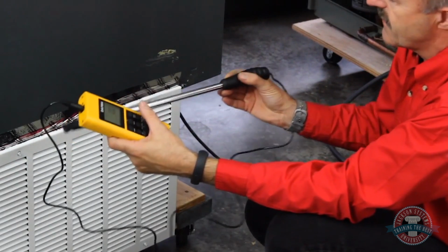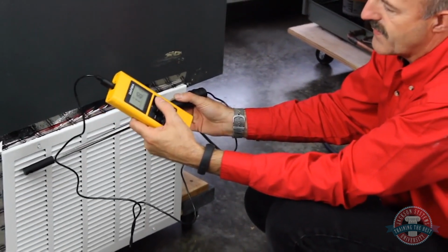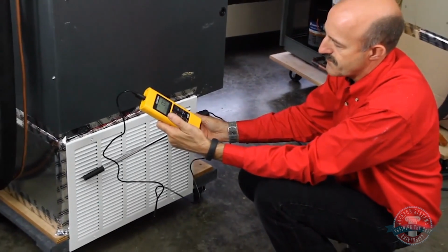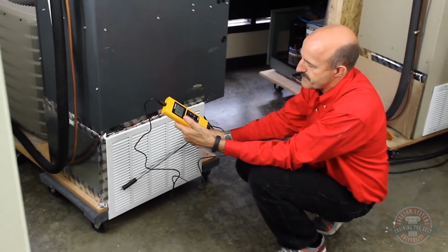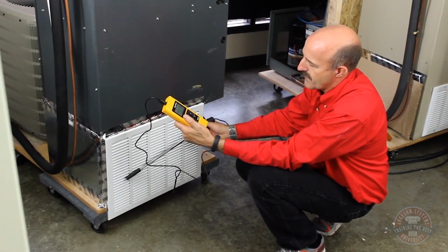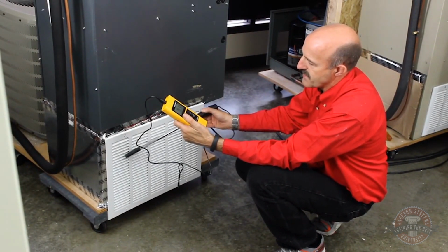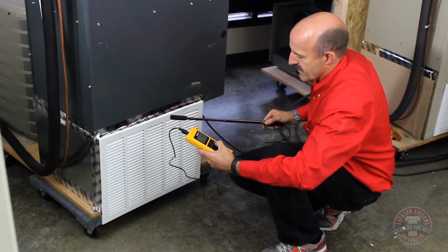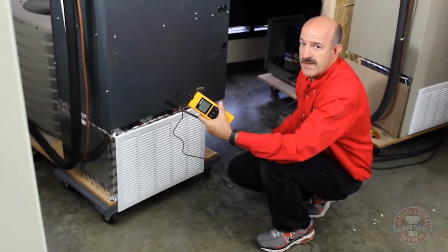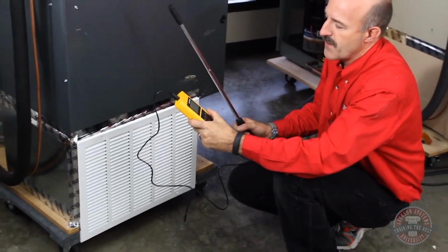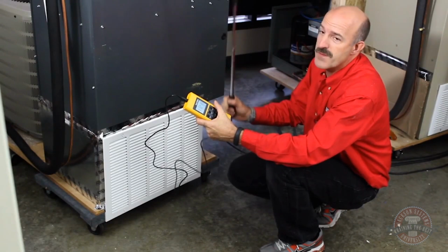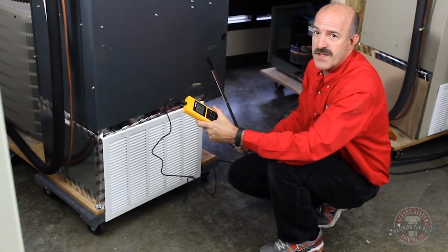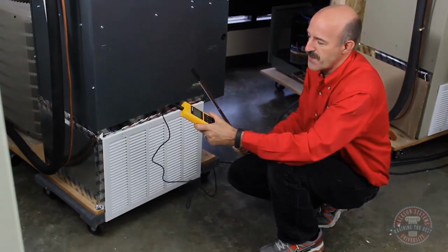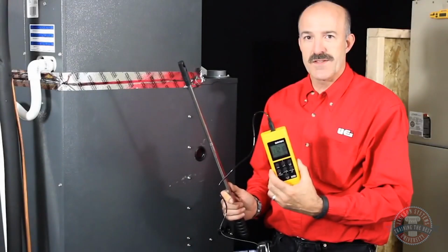Again, air in, so I got the direction of the airflow, and I hit start. You basically paint the surface of the grill. Done, you hit stop. The average, 1120, 1150. I'm within 30 CFM, so we have a 3-ton system. It's about 400 CFM per ton, so good with the setting for the airflow in the system. That's the DAFM4 small vane in-duct anemometer from UEi. Thanks for watching.